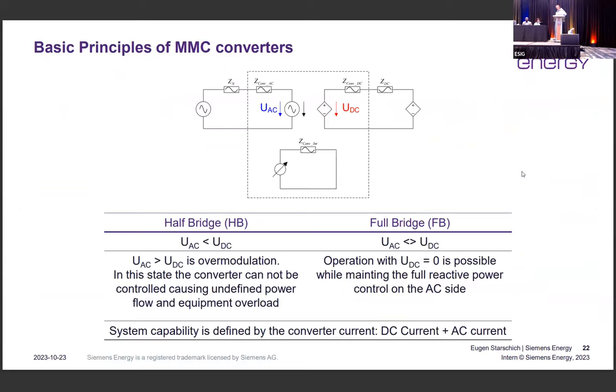So, looking at the MMC converters, this is the basic principle. From the control point of view of the VSC converter, if you look at the control structure, and this will probably be similar for all the vendors, we have three different control loops. One is towards the AC side, one towards the DC side, and one is the internal control loop. Towards the AC side, it's straightforward.